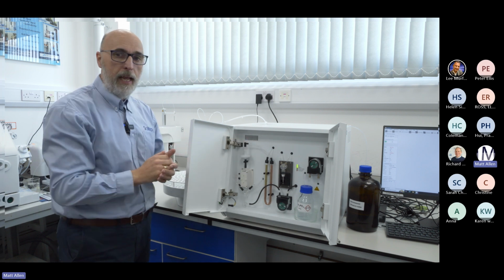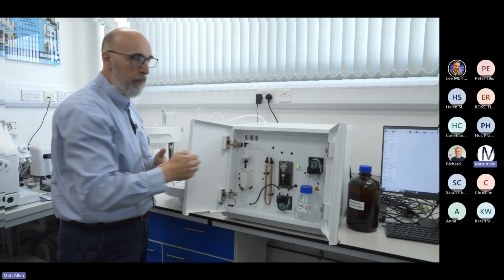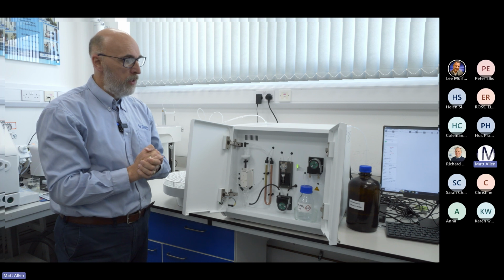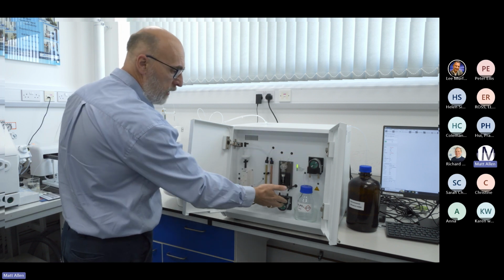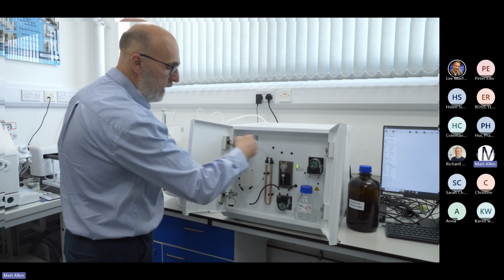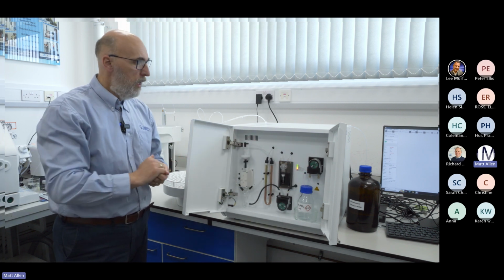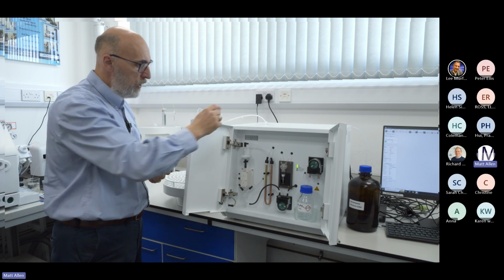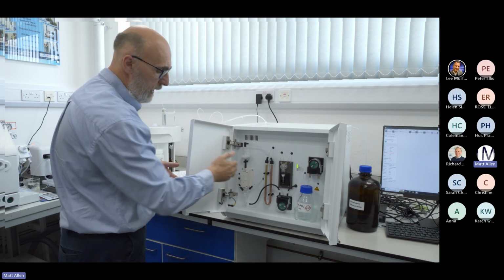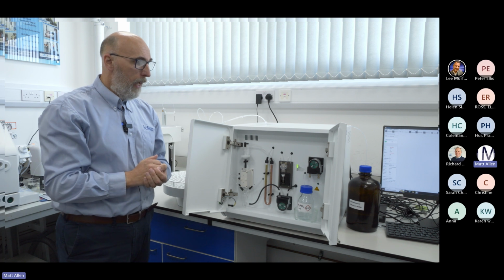Our sample loop, which sits here, means that the sample never comes into contact with the syringe pump, so you can rinse, you can dilute without having any fears of contamination if that's something that concerns you. And then we've just got some other basic pumps here, one going to waste, and this is for the phosphoric acid, for the TIC, the inorganics measurements. But the sample goes to the autosampler, combustion chamber, through the filters, through the halide scrubber, through the inorganics chamber if necessary, on its way to the detector, and it's being carried by one of two carrier gases. We use either oxygen or synthetic air, nice and easy to install, and that's the sample path, and that's the frontline maintenance. And handing back to Richard, who's going to show you some additional features in the software.